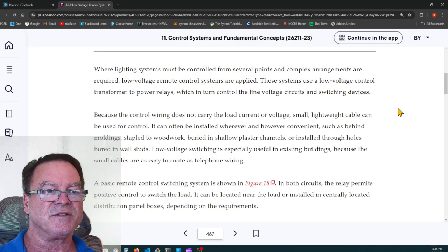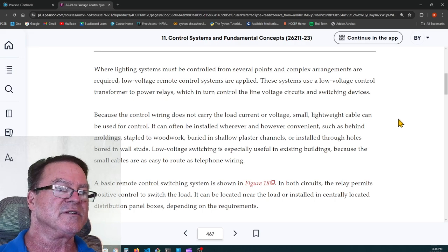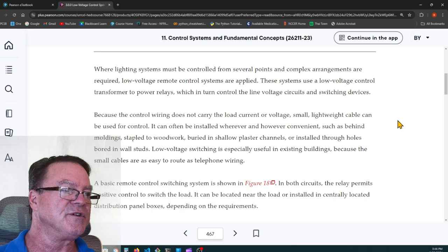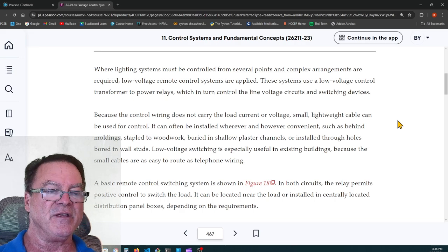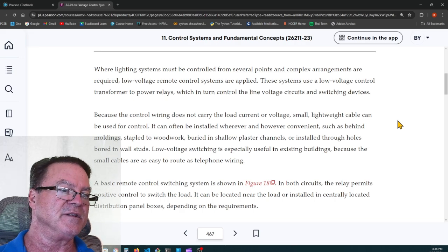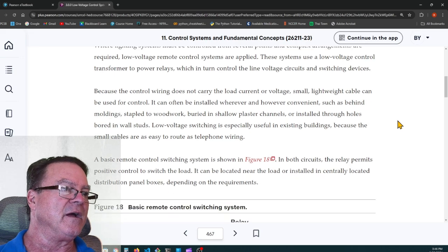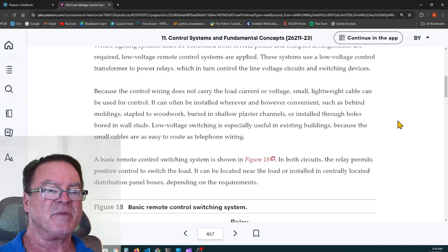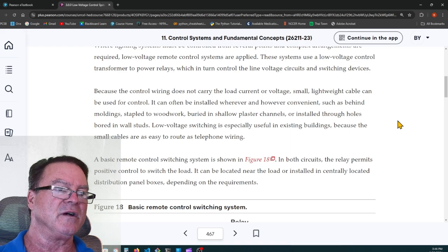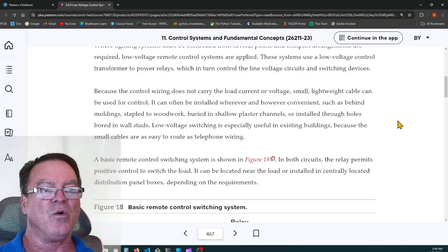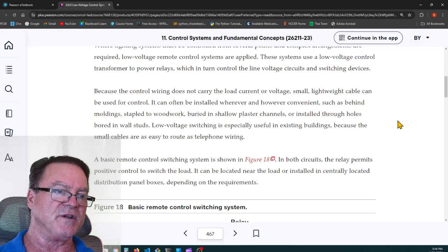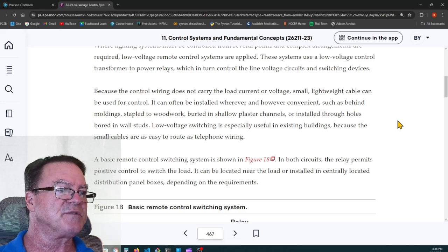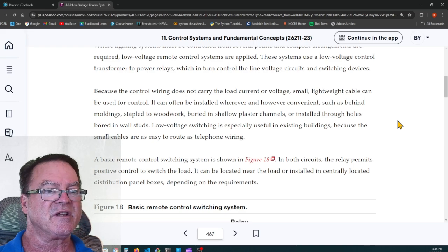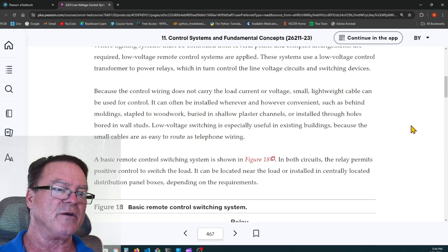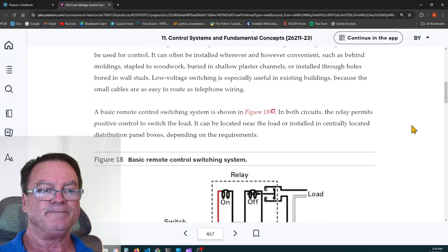circuits and switching devices. Because the control wiring does not carry the load current voltage, small lightweight cables can be used for control. It can often be installed wherever and however convenient, such as behind molding, stapled to woodwork, buried in shallow plaster channels, or installed through holes bored in wall or wall studs. Low voltage switching is especially useful in existing buildings because the small cables are easy to route as telephone wire.